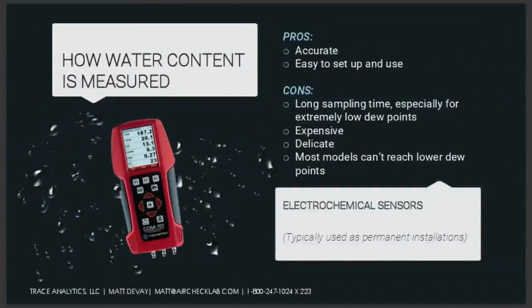All right, water content. One of the most common ways to measure water is electrochemical sensors. These detect water vapor by using materials whose resistivity or capacitance change in the presence of water vapor. They tend to be fairly accurate and pretty easy to install. The problem is they have very long equilibration times. They really like water, and so once they have water on the sensor, it takes a very long time to flush that water off the sensor and have it reach equilibrium. So they tend to be mostly used for permanent installations.